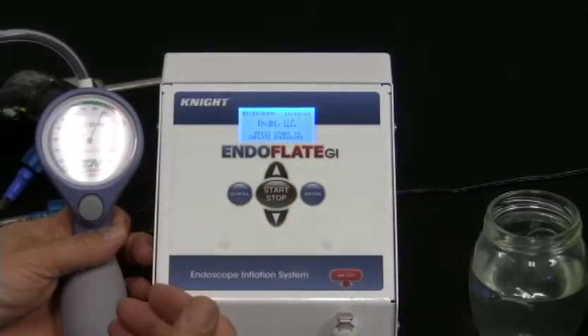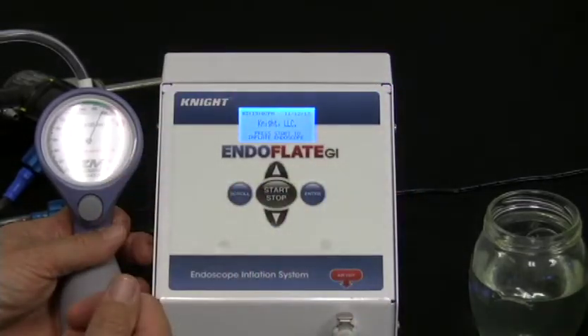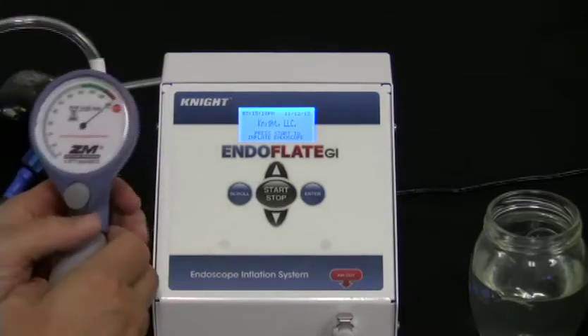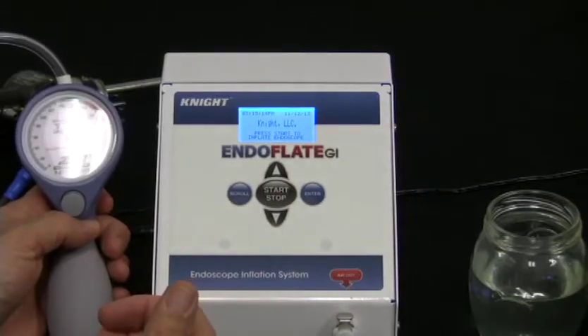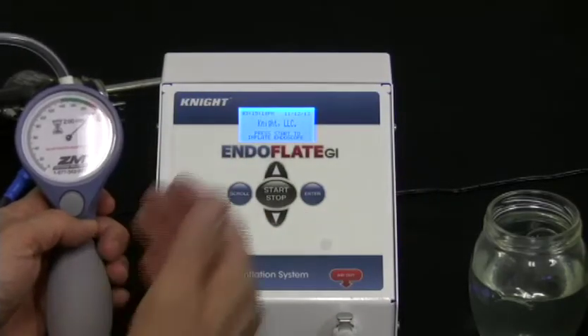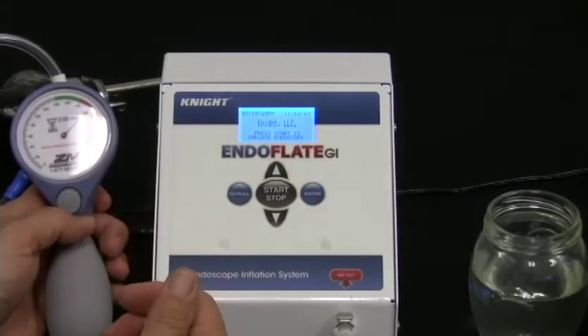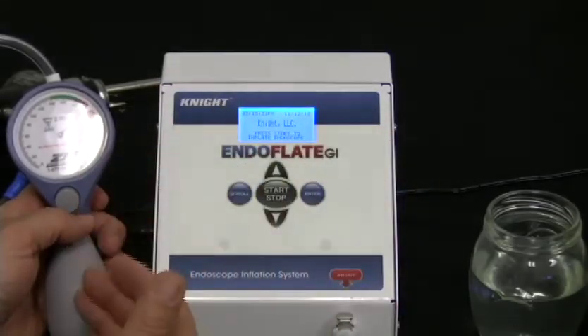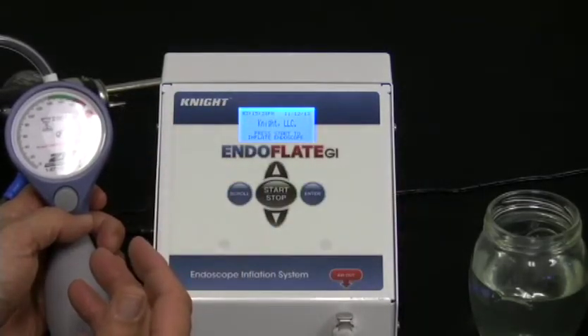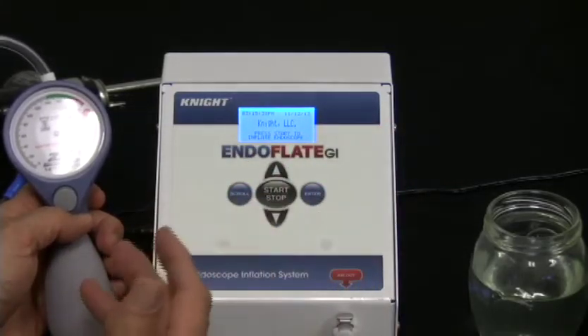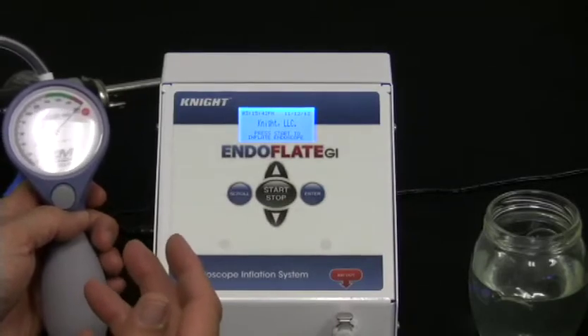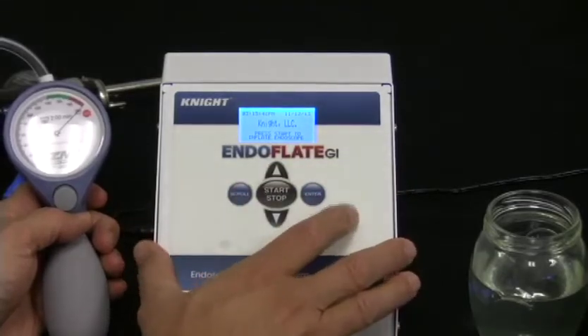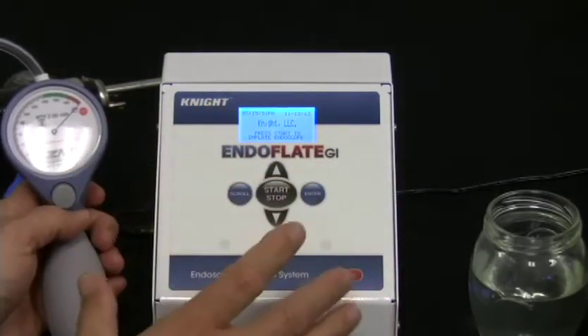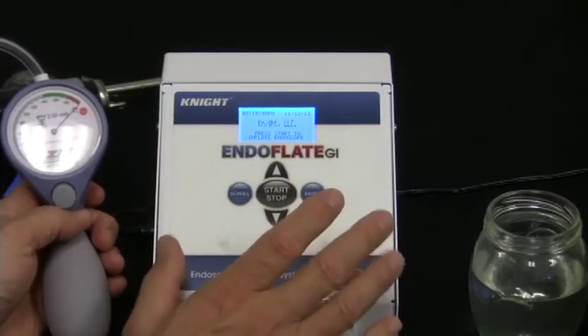All we're doing with this device is mimicking this operation with a higher level of precision, but basically giving them a method of inflating the scope without having to do all this manual pumping. It also prompts the technician through the testing. People like gadgetry, so having a display, a nice user interface, I think is going to attract some people, but it's easier to use and, like I said, a little bit more precise. It'll give you the numeric values. And when people see those kinds of display elements, I think they believe more that the device is more precise, and they're just getting a better overall test. So that's really the general philosophy behind our EndoFlate. It's an inflator. It's not a leak tester. I have to bring a lot of emphasis to that, because this is not to be sold as a pass-fail device.